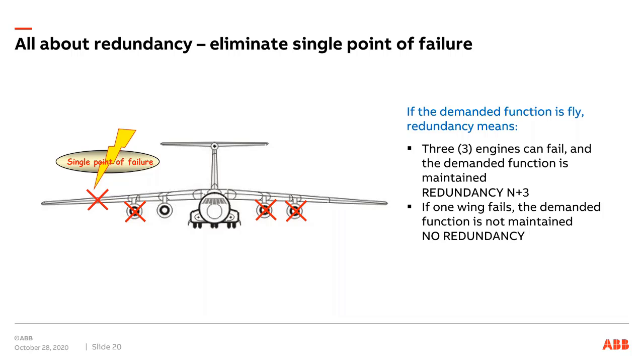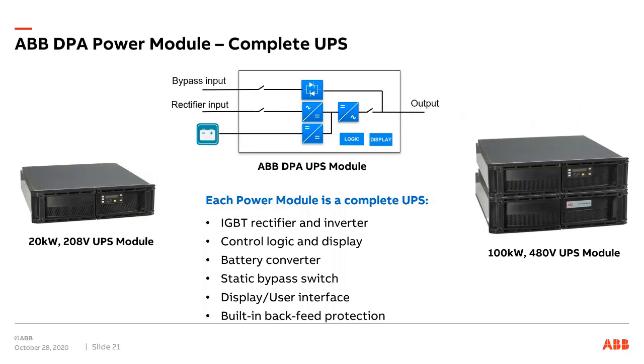And so the whole design, like a UPS, customers get a UPS for a reason, and the design evolves and improves to eliminate, or try to eliminate, every single point of failure. I don't know if the airline industry will ever get beyond this one, but it may not be that likely that the wings should fall off a plane. But just as a parallel, something to think about if we ever get back up flying again.